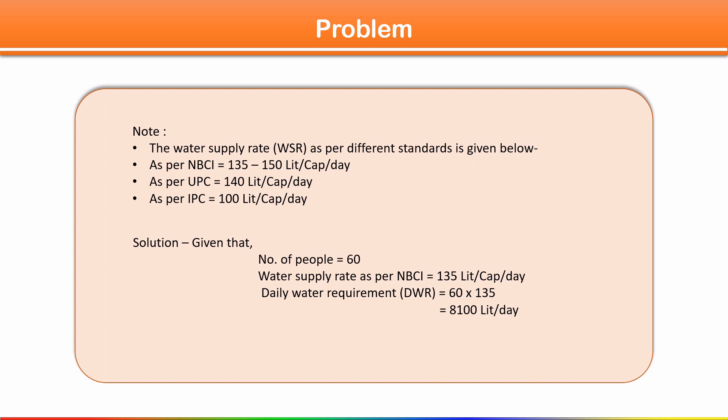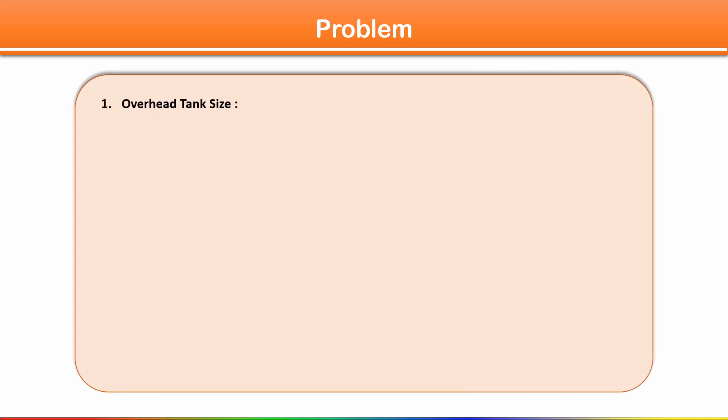The daily water requirement is 8100 liters per day, which is 8.1 cubic meters per day. To find the volume of the overhead tank: since OHT is designed for half day capacity, volume = 8.1 × 0.5 = 4.05 cubic meters.